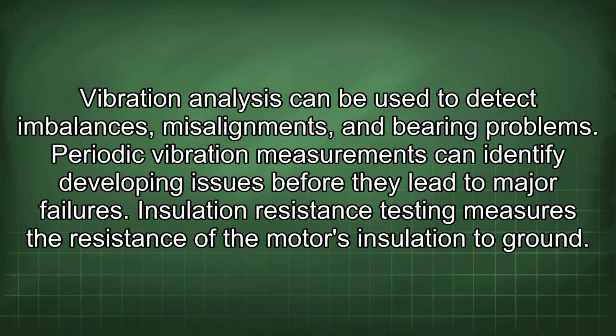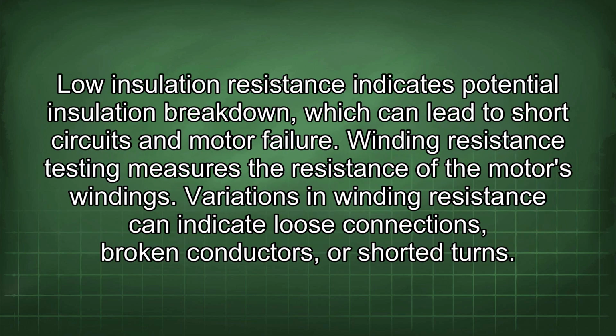Vibration analysis can be used to detect imbalances, misalignments, and bearing problems. Periodic vibration measurements can identify developing issues before they lead to major failures. Insulation resistance testing measures the resistance of the motor's insulation to ground. Low insulation resistance indicates potential insulation breakdown, which can lead to short circuits and motor failure. Winding resistance testing measures the resistance of the motor's windings. Variations in winding resistance can indicate loose connections, broken conductors, or shorted turns.